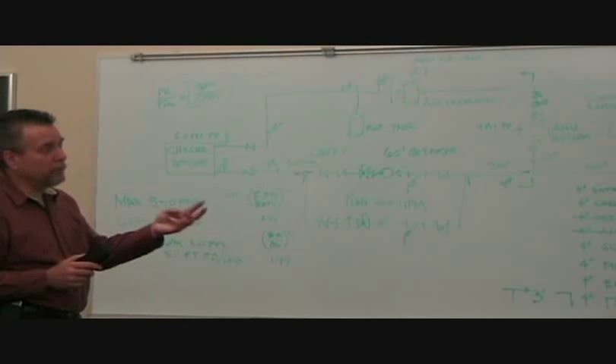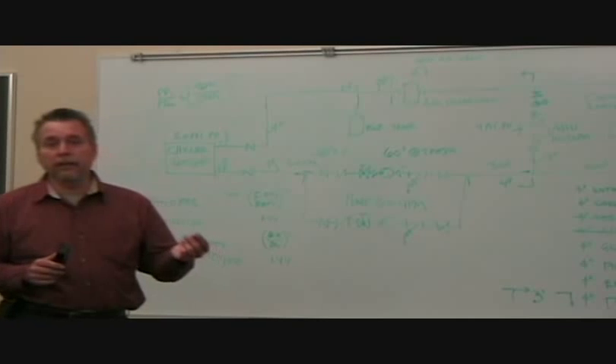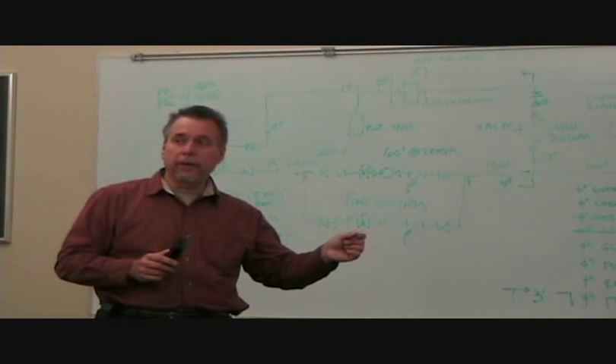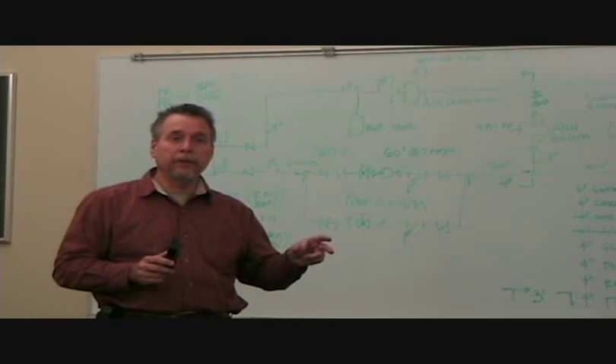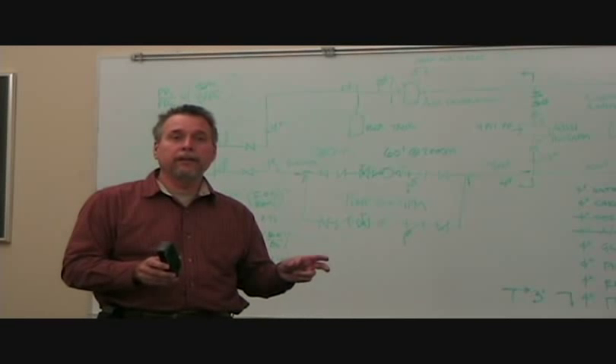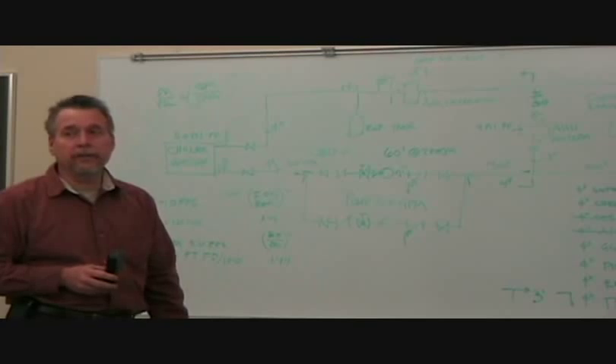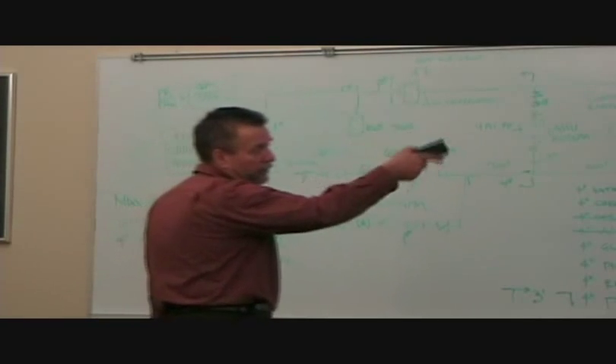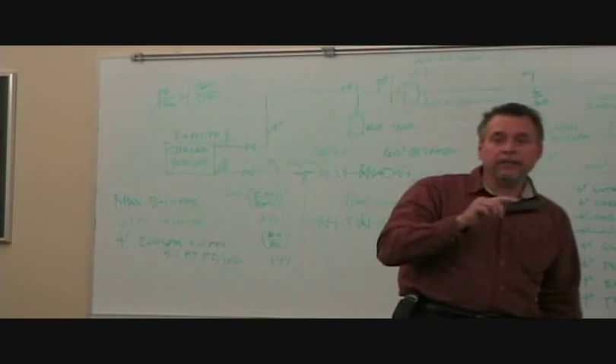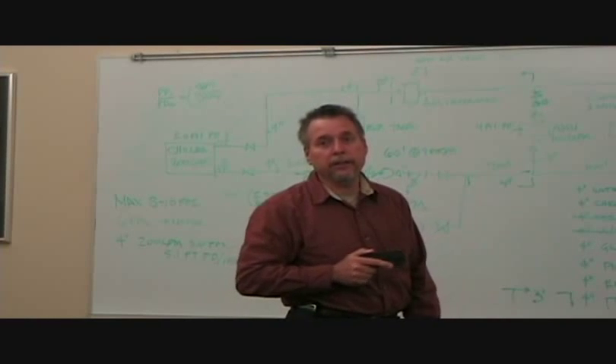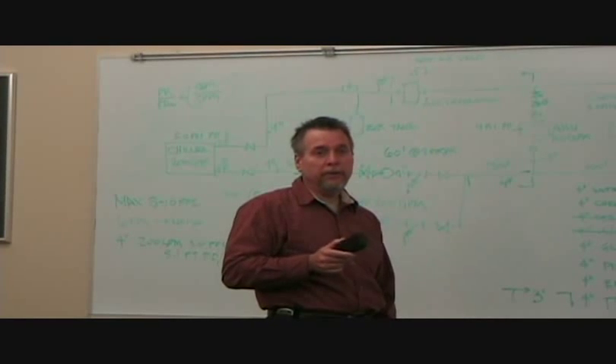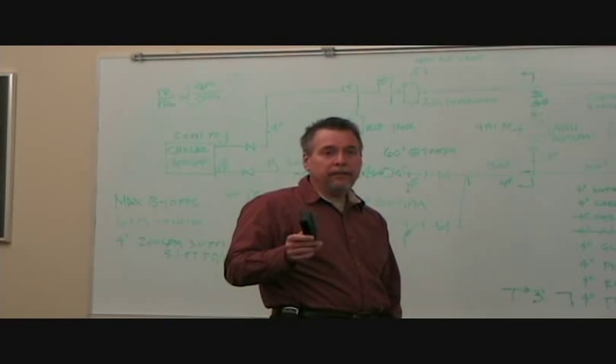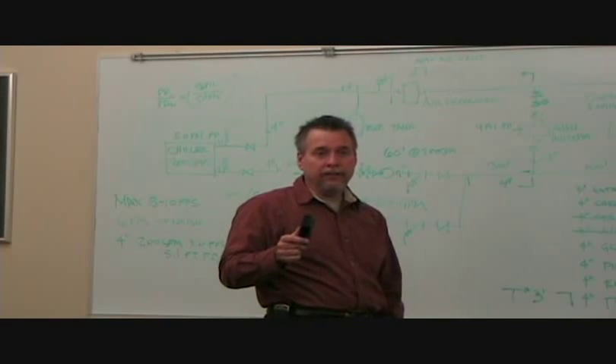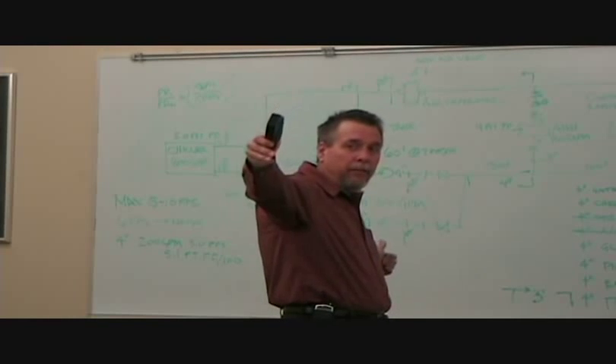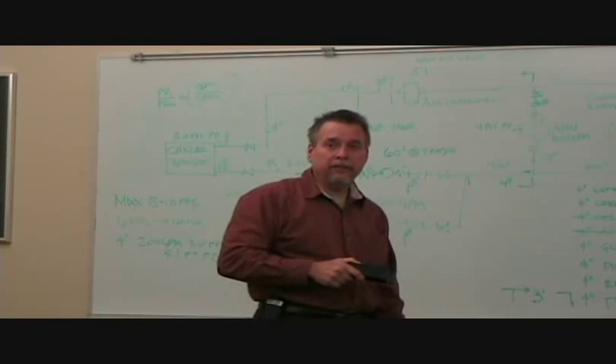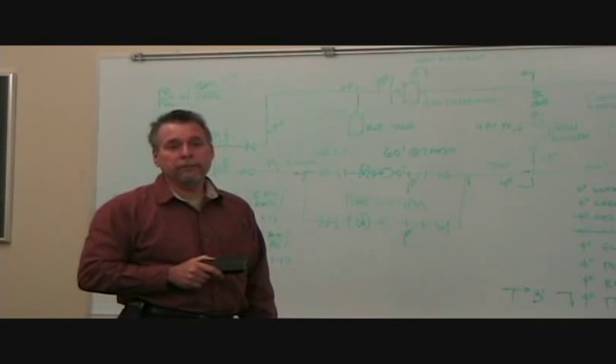We'll do one for chiller, one for cooling tower. We'll see the net positive suction head we talked about the other day, how to make sure that your pump won't cavitate when it's operating on the cooling tower side. And we'll talk about elevation differences and go through the calculation process of calculating net positive suction head. It's pretty simple once you've done it once. Go through the calculation, and unless you've got a tremendous length of pipe, any elevation where the cooling tower is above the pump will work.